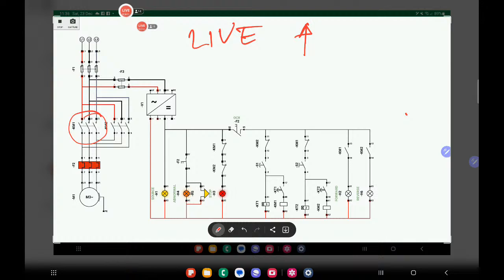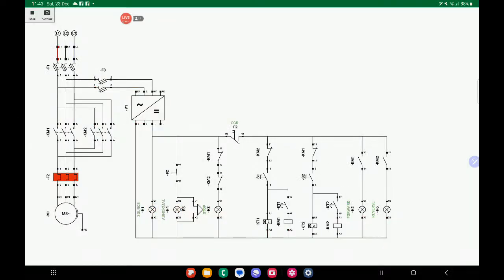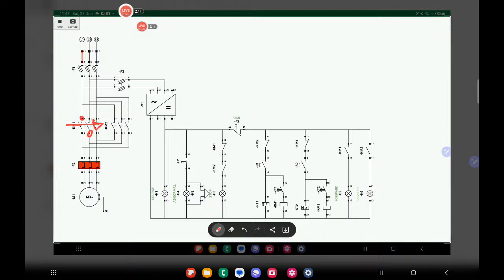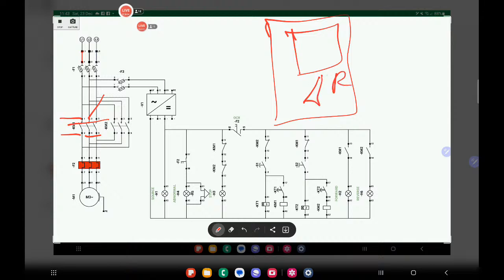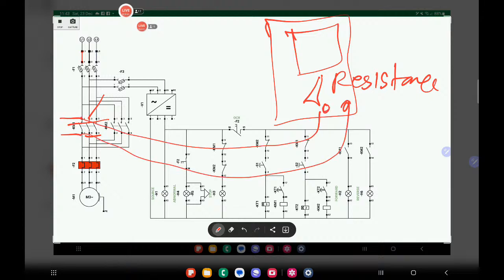So by pushing, you have to stop the operation, and then that's the time you need to do a manual activation, pushing it, and then again apply the same. Since it is a dead circuit, try to push it and then just do a continuity. So turn your multimeter into resistance, and then do a continuity test on the line to line. There should be a closed contact. There should be a continuity. Check all the lines, the resistance, the continuity, if they are in good condition while you are pressing or activating the main contactor manually.